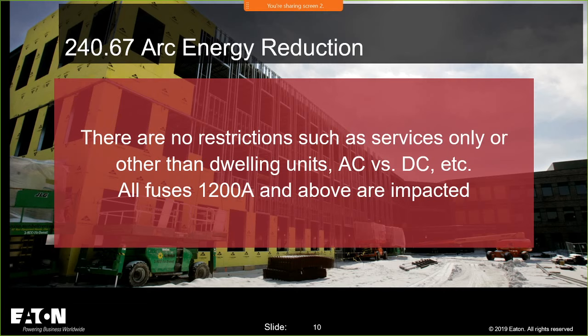Now, I have to tell you there is one restriction. If you go to 240.1, and this was brought to my attention last week when I think I showed this same slide, 240.1, the scope of Article 240. Remember in yesterday's class, in the very beginning, we talked about articles, parts, sections, and things of that nature. 240.67 is in part, I think, 6 of 240. Yep, part 6, cartridge fuses and fuse holders. If you look at 240.1, it tells you parts 1 through part 7, and we're in part 6. Parts 1 through 7 of this article provide the general requirements for overcurrent protection and overcurrent protective devices not more than 1,000 volts nominal.